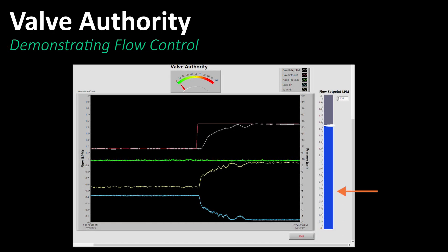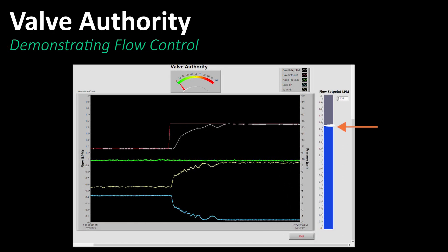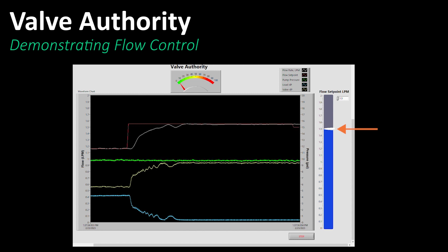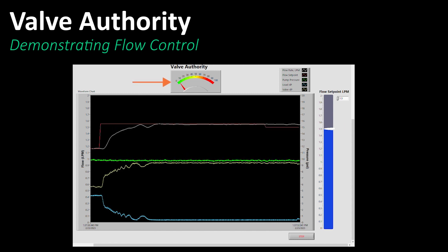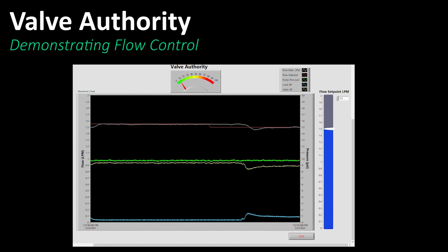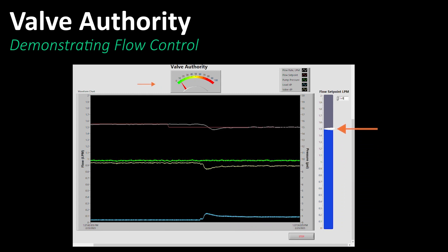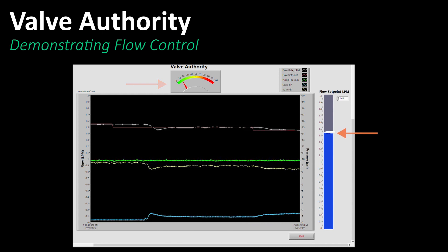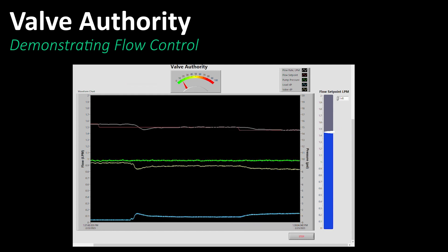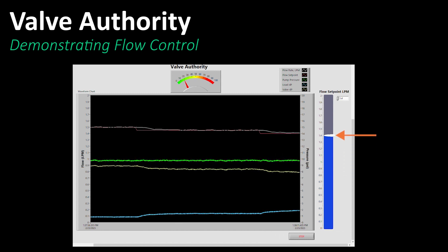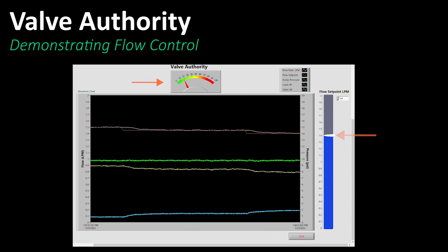Let's lower the flow setpoint from 1.55 to 1.5 — this increases authority from 2% to 10%. And lower the flow further to 1.45, increasing the valve authority further to 15%. And finally, lowering the flow to 1.4, increasing the valve authority to 20%.